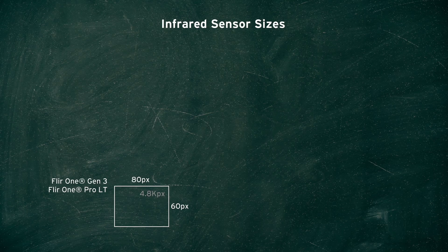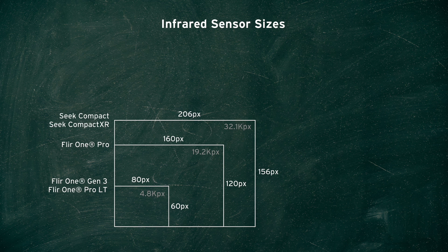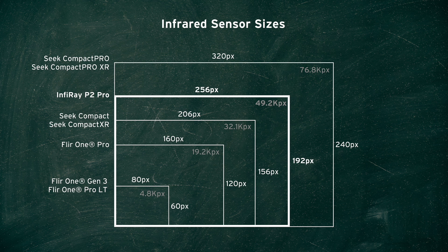When we talk about digital camera resolutions we often talk about megapixels, but this is not the same with thermal cameras. The FLIR One Gen 3 has a thermal sensor of only 80 by 60 pixels — or 0.005 megapixels. We'll be using kilopixels to describe the different thermal sensor resolutions. The FLIR One Gen 3 is a 4.8 kilopixel sensor; the newer FLIR One Pro has a 160 by 120 pixel sensor or 19.2 kilopixels. The Seek Compact has a 206 by 156 pixel sensor, and the Seek Compact Pro is 320 by 240 — that's 32.1 kilopixels and 76.8 kilopixels respectively. The P2 Pro has a resolution of 256 by 192 pixels, or 49.2 kilopixels.